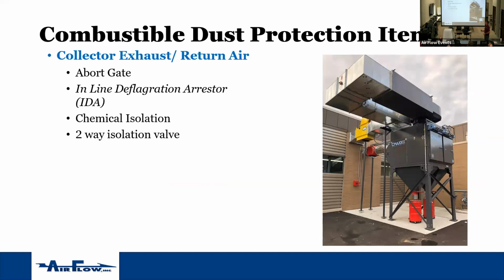All right, on your exhaust, on your return side, the clean air side, not the discharge. Remember, discharge is down here. So clean air coming back into your building. You have the abort gate. The abort gate itself will stop smoke from going back into the space. You only need an abort gate if you're returning the air to the space. There's no other reason to put an abort gate in if you're just going to blow it outside in the atmosphere. You need your inline deflagration arrestor if you're going to return the air to the space. That stops that flame from going back into the space, causing that secondary explosion.